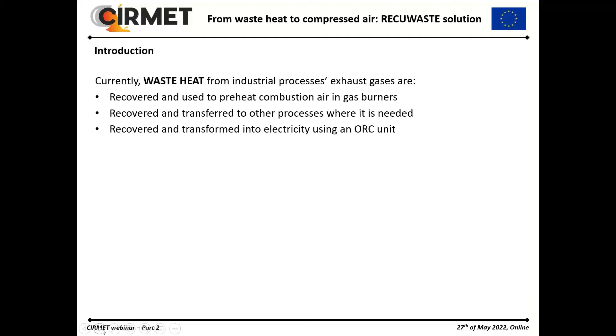The system is designed to recover heat from waste gases and transfer it directly into mechanical energy to feed an air compressor, with the possibility of storing excess energy. It is more efficient than a traditional ORC, as the generator and motor are removed: the air compressor is directly driven by the shaft of the ORC expander, so the ORC doesn't need a generator and the compressor doesn't need a motor.